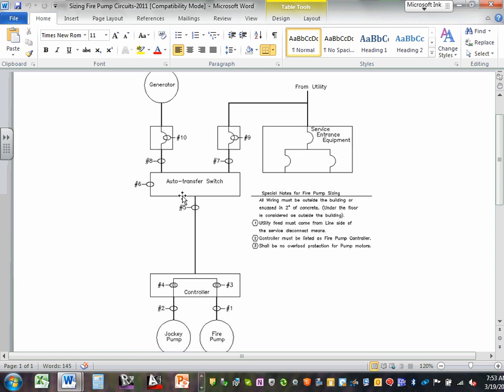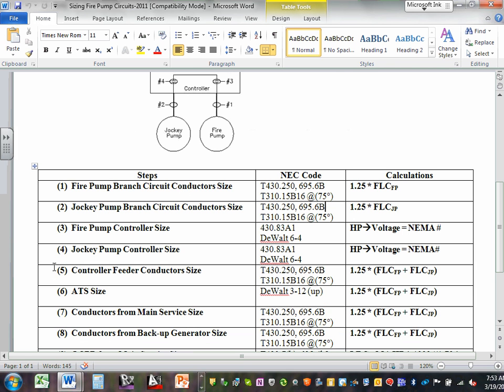Number 6 says auto transfer switch, right? Can you see them? For the auto transfer switch, it says when we size it, we go to the NEC 3-12, and we go up if it's not standard. And how do you calculate it? Based on the amps, you take 1.25 times the sum of the fire pump full load current and the jockey pump. Does it make sense, guys?